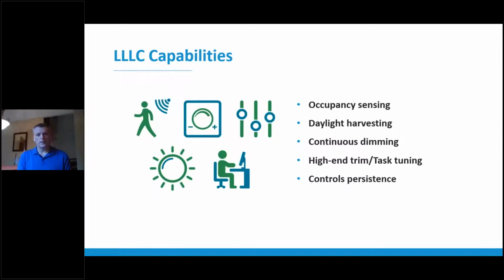thing and no controls. The other one that we'll talk a lot about in this case is the high-end trim or task tuning. That one is important in that it allows you to lower the highest point of the fixture's power. So if it was a 30-watt fixture and you trim it 50%, the most that fixture would use is 15 watts. So these are all the capabilities that are required as a base for everything.